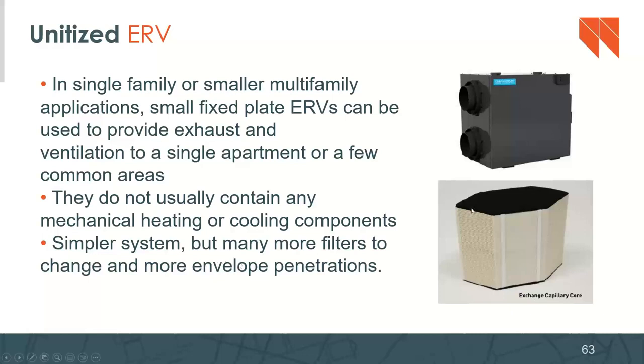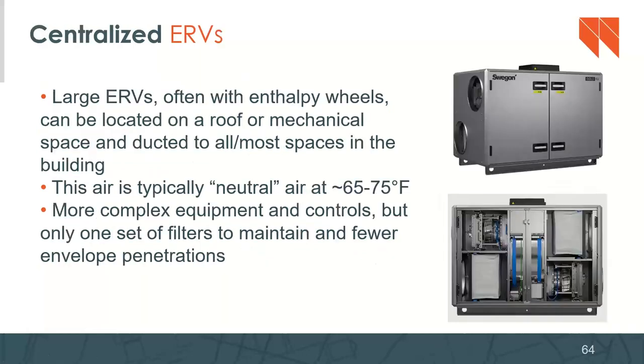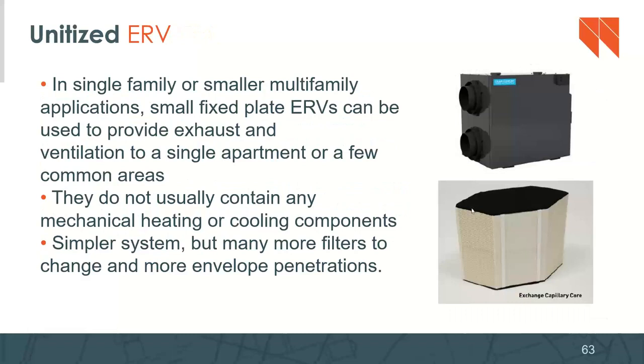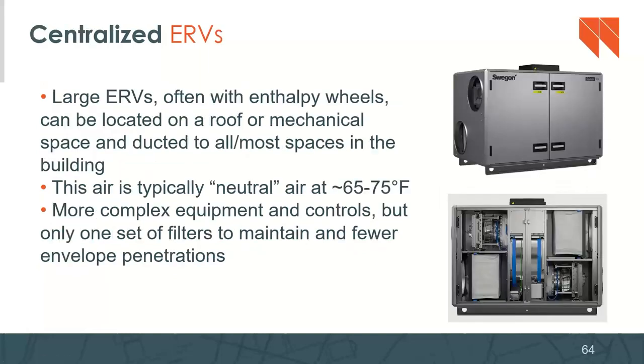So in terms of making a decision for a multifamily building, whether you're going to go with a central system, a large centrally located ERV, usually on the roof, or many multiple individual ERVs, these are the considerations that we want to talk about. The biggest downside with individual units is there are a lot more filters to change. There are a lot more envelope penetrations to mitigate. With the central ERV, these things are mitigated. You only have a couple of filters to change on one, two, or three pieces of equipment at most, right?